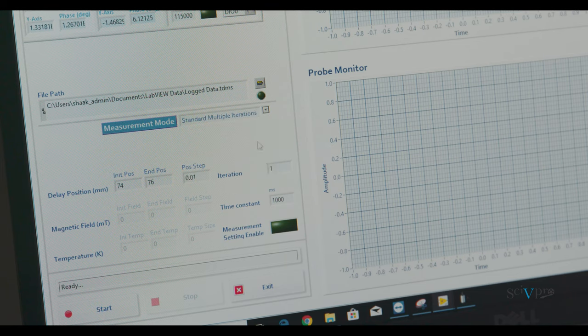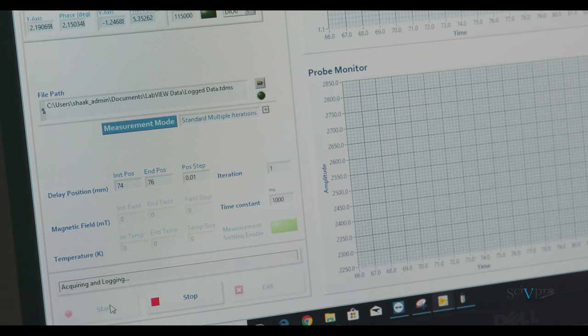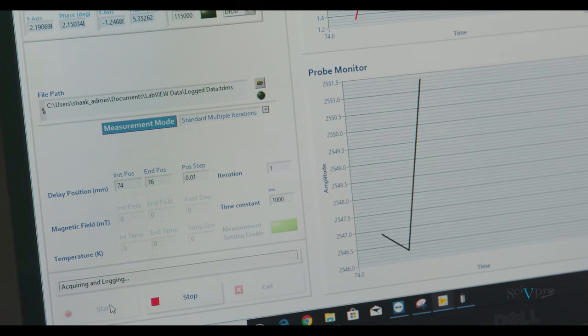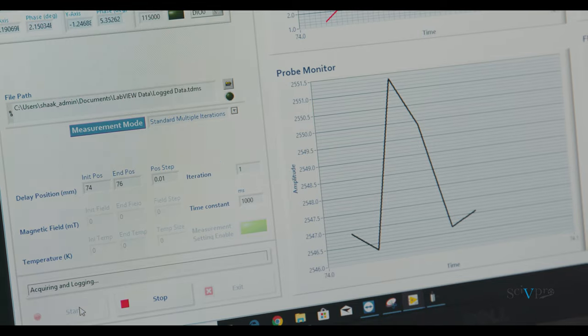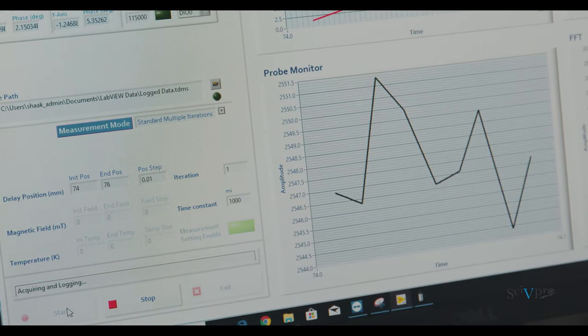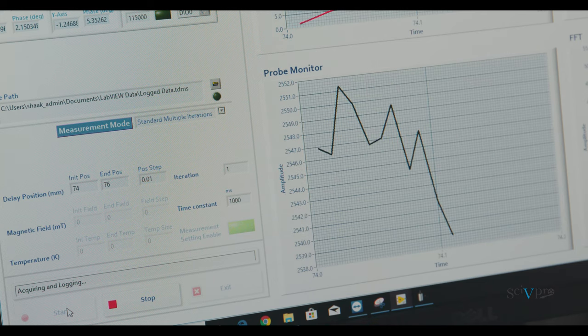To start a new measurement, select standard multiple iterations from the terahertz time domain spectroscopy control software. Click on measurement setting enable and press start. The probe monitor represents the probe pulse used for the electro-optical sampling. The probe must be stable, with a maximum deviation of 1% from the baseline.